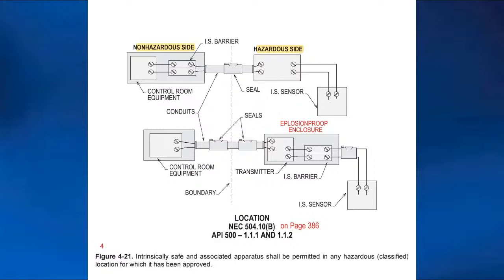But now, one thing you want to look at here, fellas, is that in the non-hazardous area, you want to put that enclosure that has your barrier. Then it can be just a general purpose enclosure. Then you just put your seal at the boundary or the imaginary boundary. And then you notice you don't need any seals leading there on that hazardous side. Right. Process instruments and things like that have a great pressure.